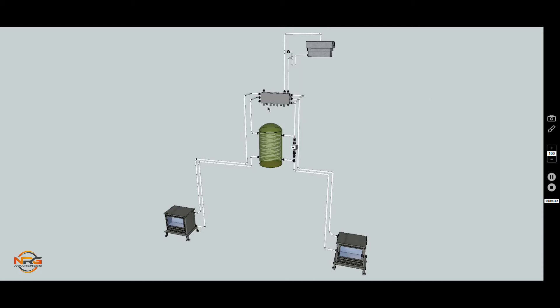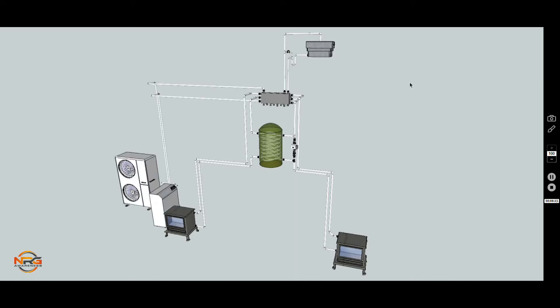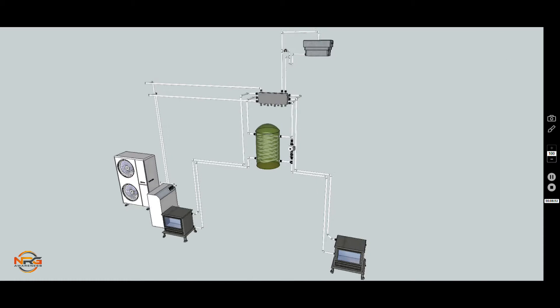Now if we wanted to introduce a heat pump at this point in time, we have an opportunity to introduce it, bringing the heat in a flow connection that's available at T1, and the return going back from here. So if we put in a heat pump, the heat pump would be extracting the heat from the air outside the building, converting it into water-based heat with this plate exchanger, and delivering that heat into the manifold, flow on top, return going back to the heat pump from the optimum location, which is the return port or the lowest side port, which is L3 in this example, of the manifold.